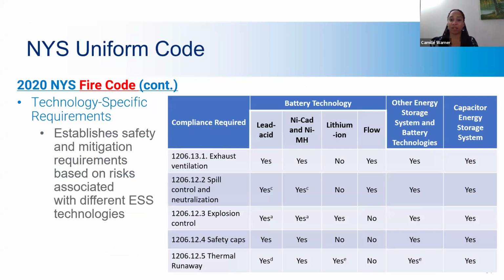Continuing on into the fire code. The thing I really like about the New York State Fire Code is that it understands that battery technologies are unique and different. Different electrochemical technologies are regulated based on their different chemistries. And this table does a really great job of illustrating that. In lithium ion systems, which is this row right here, exhaust ventilation is not needed during normal charging or discharging, so it's not a requirement. Spill control and neutralization is not necessary because during normal charging and discharging, the electrolyte is contained. It can't spill. It's in an enclosed vessel. But explosion control is a requirement. If you comply with NFPA 68 or 69, you comply with the fire code requirements.